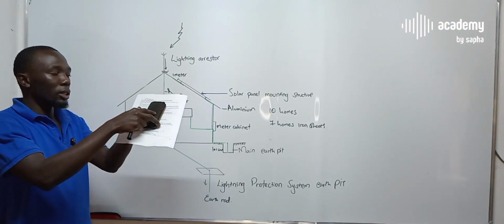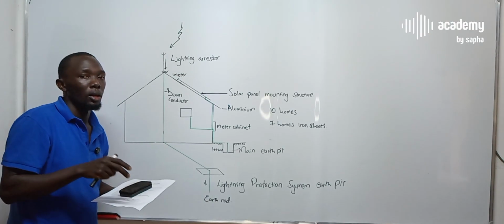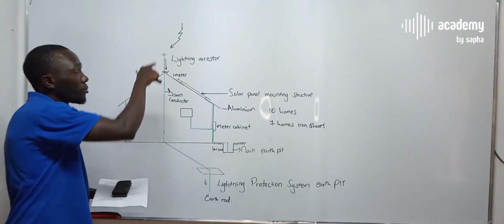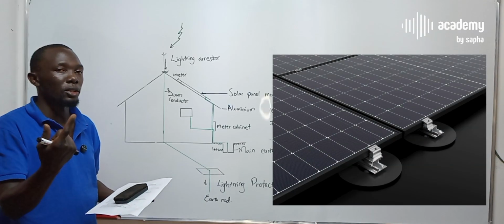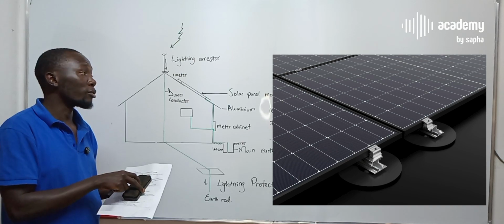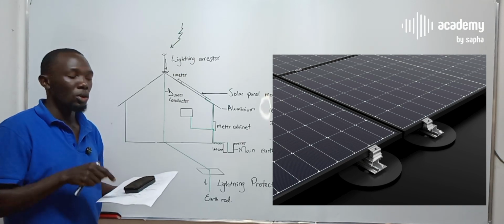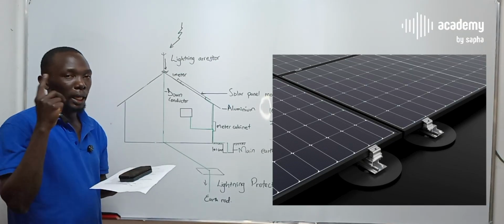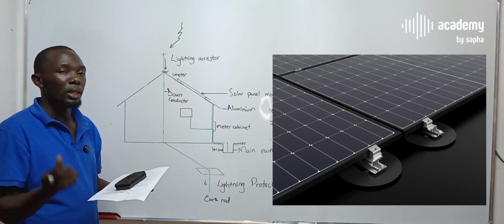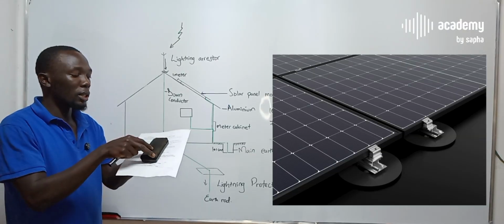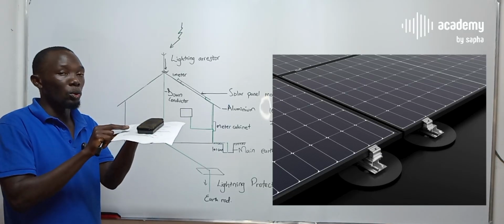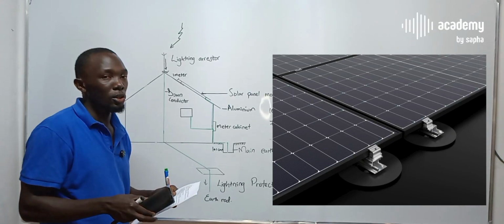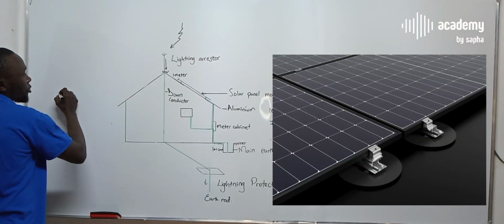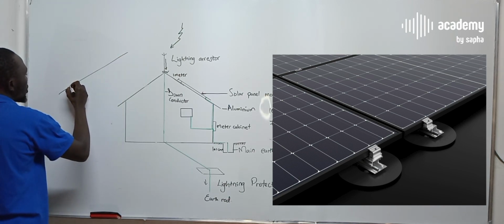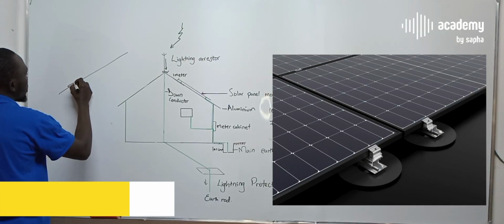So when you mount your panels over the iron sheets, what happens is that in case of a fault, the iron sheets might conduct through the metallic structure of the solar panel frames and damage your solar panels. So you are encouraged to use another insulative or insulated barrier between the metallic frame of your solar panels and the roof structure. So essentially that means that you should also have at least 2 layers. By 2 layers, I mean, if this is your roof, if this is the surface of the roof, you first come with an insulated material, you mount it here.